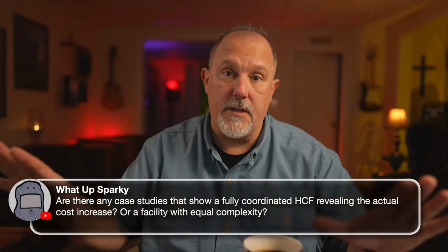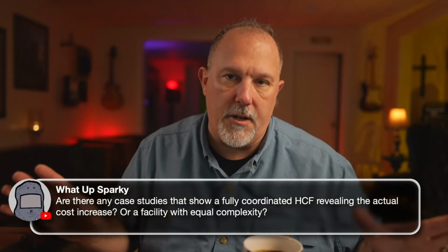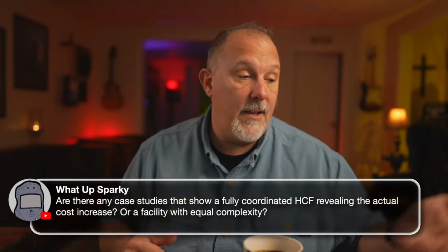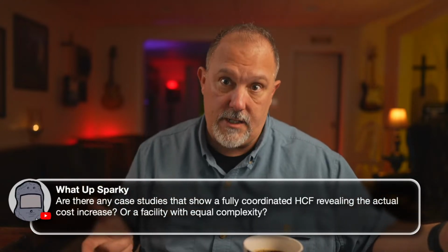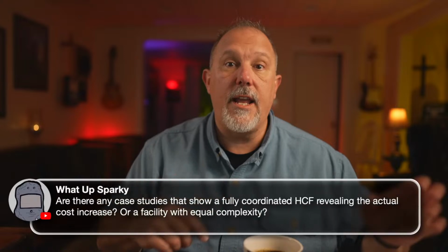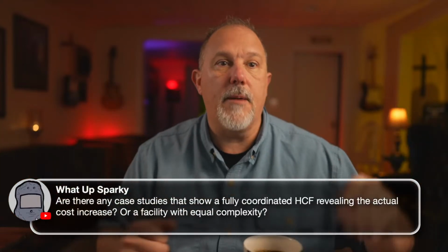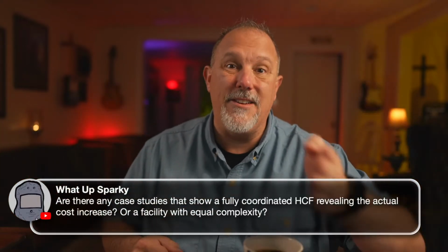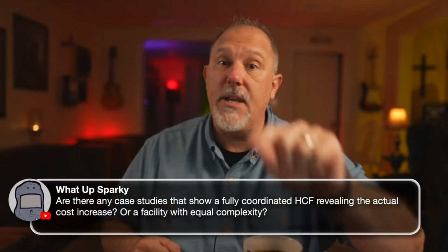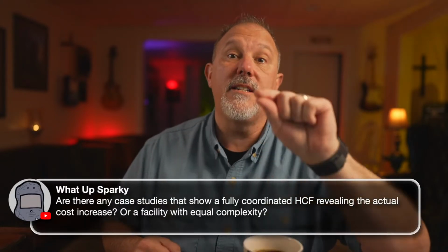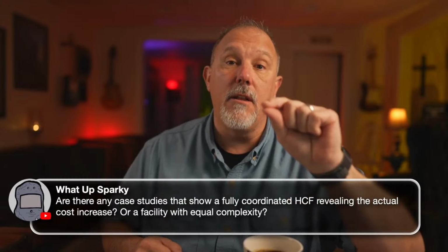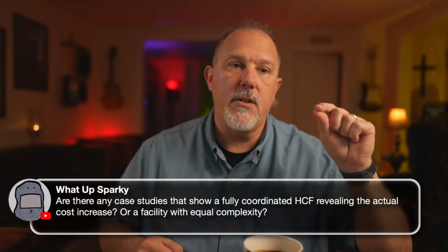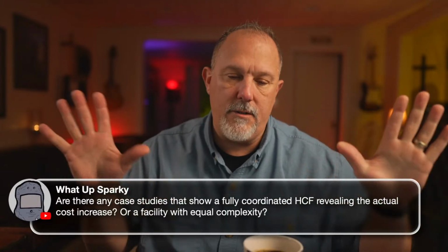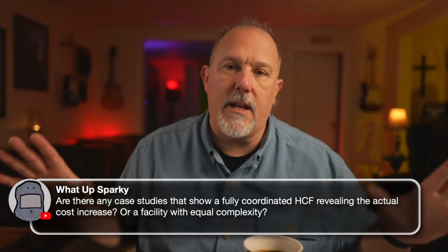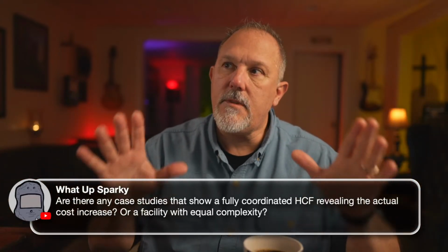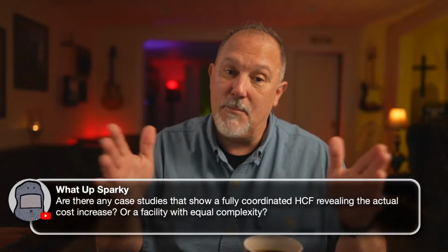I explained the difference. And I try to stay out of the debate and argument. I mean, if you want my opinion, I'll tell you. If you're doing 0.1 seconds, you're crazy. If you're saying I'm not doing selective coordination, but I'm going to coordinate to a lower fault current value, and you establish what that value is based upon your engineering knowledge, and you're willing to stake your PE license on it, yeah, I have a lot of respect for you. But to ignore fault current, I don't want you in my class. But in any case, that's just my opinion. I put it out there.